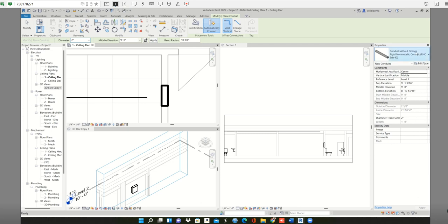When you put it very close to the panel, a lot of Revit elements have snap points. So if this is your panel and a conduit is going to here, Revit automatically will try to go down to join, I mean, to attach. But in this process you need elbows in your conduits to go this way, and Revit will try to make this, and maybe it won't have the semi elbow. So it's not the best practice to do that.